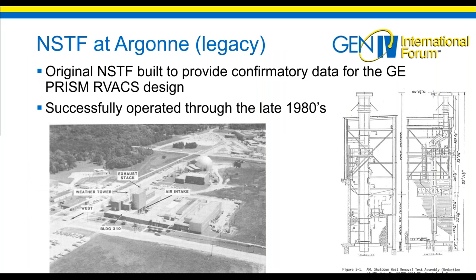The first attempts at doing these types of tests in an integral fashion were actually carried out in the 1980s, when we were working on supporting GE in the development of the reactor vessel auxiliary cooling system, or RVACS design, which is basically based on the same physics I described previously. But in that approach, the air would be drawn into the silo - basically just a large air draft cooling of the reactor vessel in that plant design.